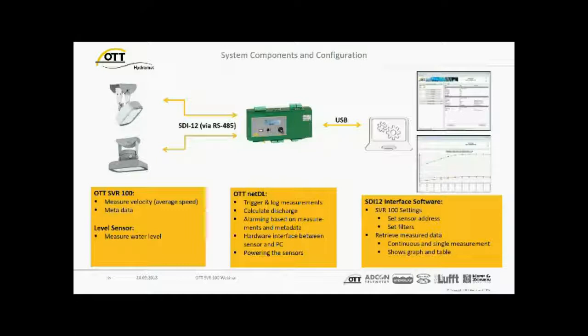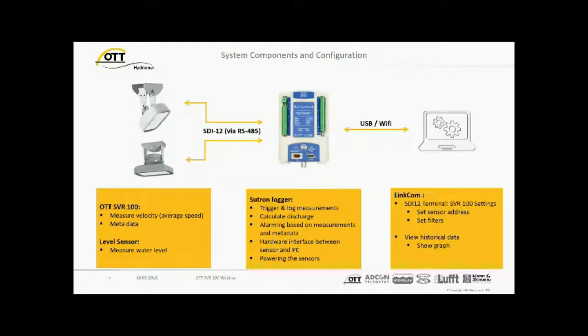You can set filters, can change the sensor address, you can retrieve measured data, you can make a graph, and so on and so on. You show graphs and tables and all these things. This is one use case. The other one is if you take one of the loggers from Sutron, Satlink, for example, Satlink 3. Here you have a Wi-Fi connection between the PC and the Sutlink logger. You can also here set sensor address, set filters, show graphs, and on the logger itself, the discharge will be computed finally.